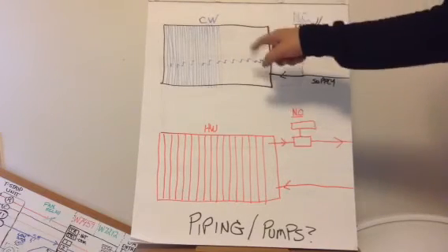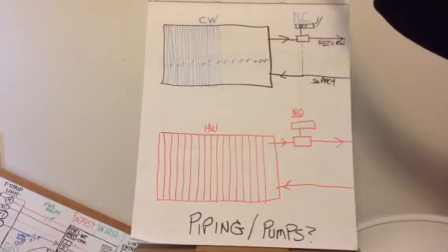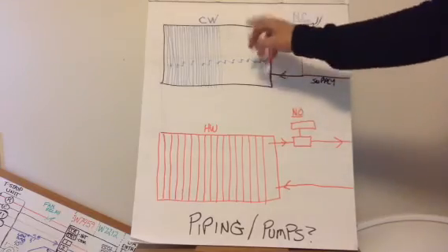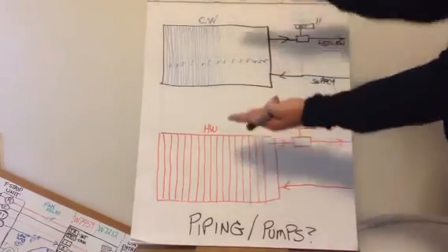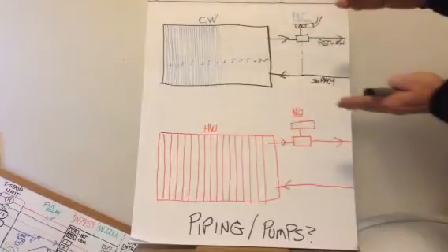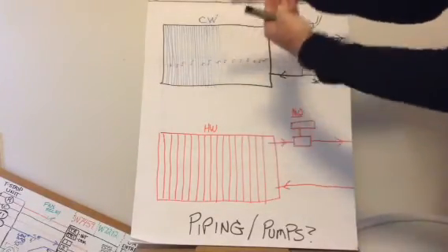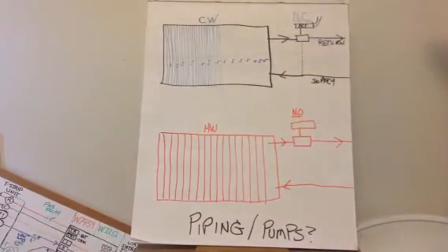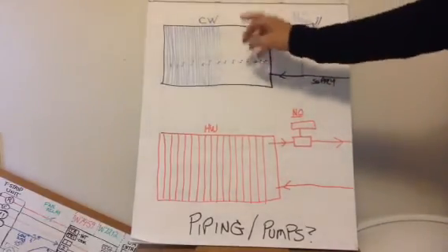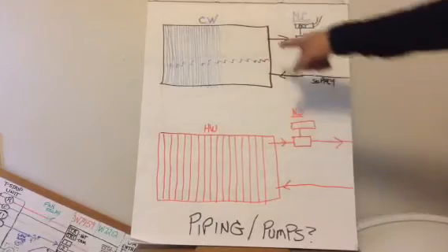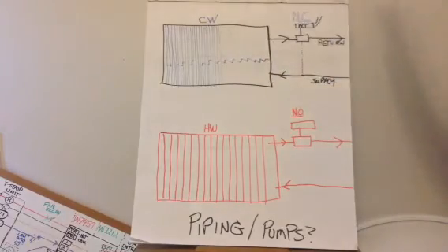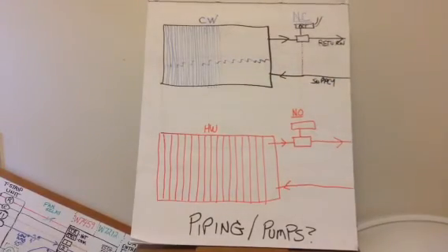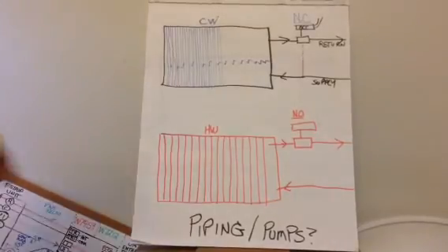So you have to open up sheet metal. You might have to cut a hole, remove panels. You've got to look at and clean the space. You know, if you had these two coils sitting like this, you can get in there and see that. A lot of times I see that second coil, just like a condenser coil when you've got to split and wash them. This coil will have all the crap on it. And that will kill your airflow, kill your cooling, obviously. So enough on that.